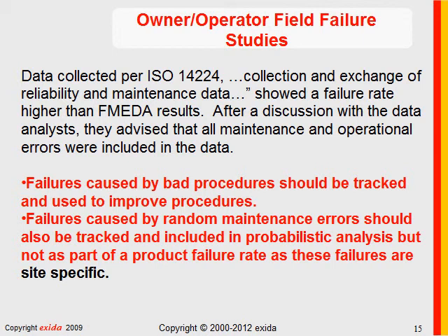In another set of data collected per a standard on data collection, ISO 14224, showed a failure rate much higher than FMEDA results. And after a discussion with the data analysts, they told me that they absolutely included all maintenance and operational errors in their data. Now, it is important that we have accurate probability of failure dangerous numbers.